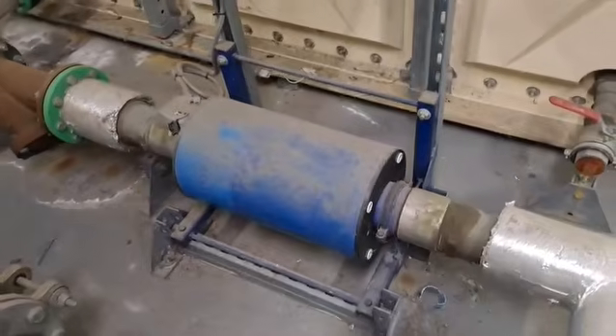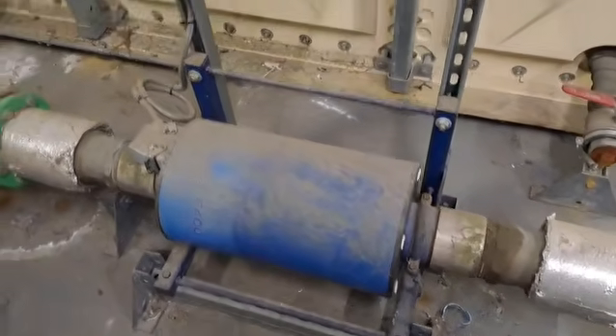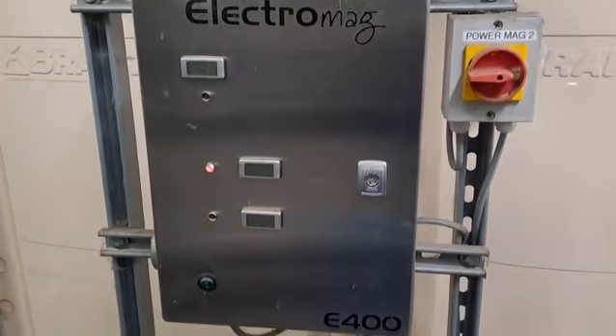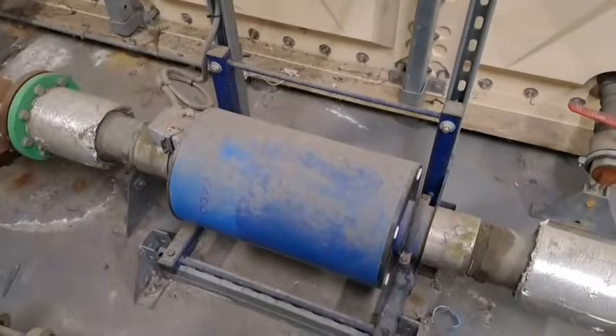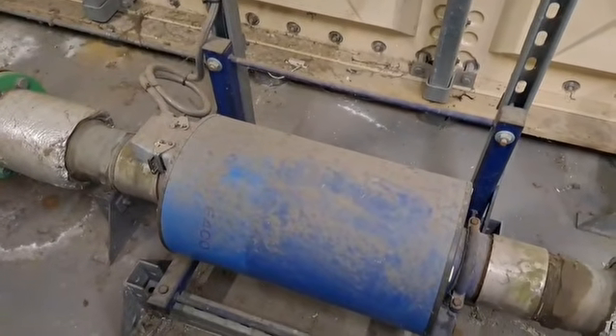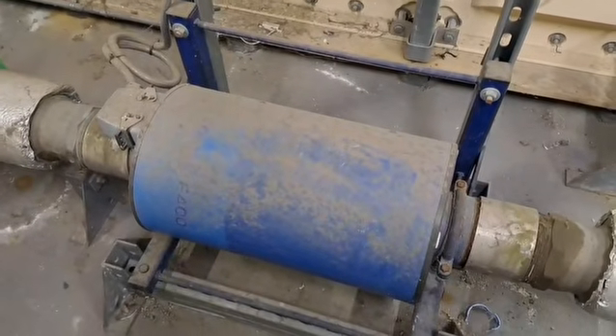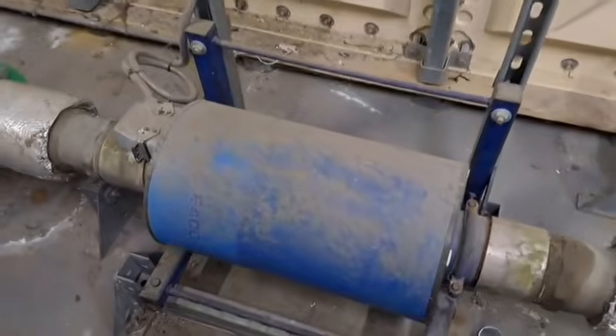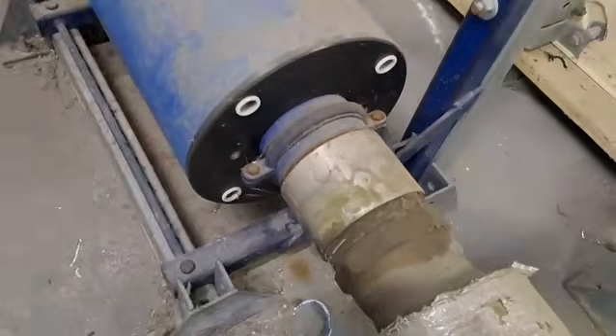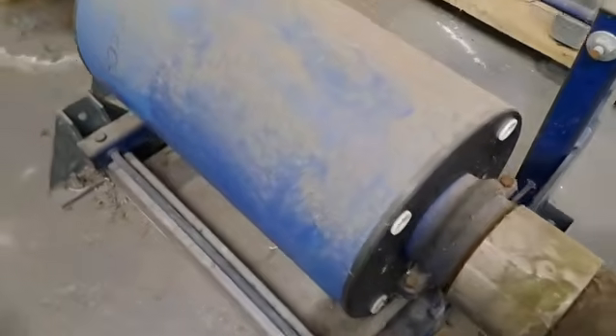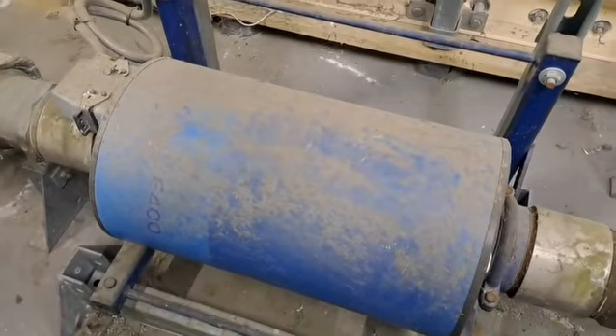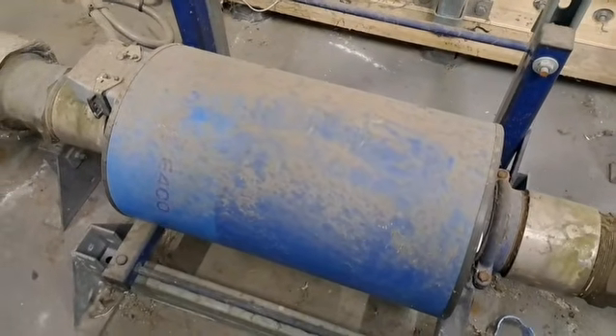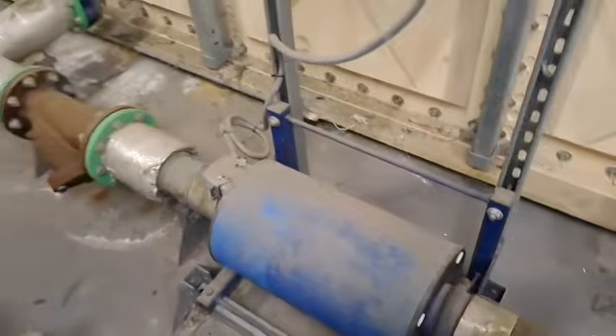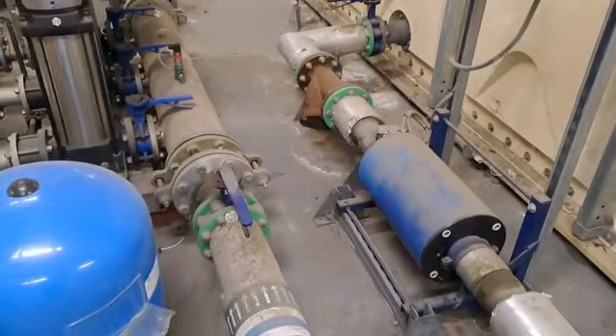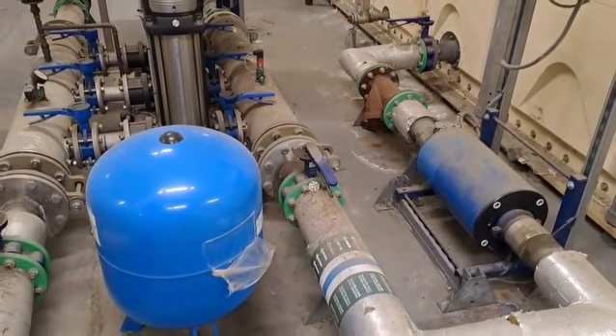and then as it comes along, you can see that we've got electromag E400s, and then down here you have the cylinder, the blue cylinder, which is the treatment coil, or you can call it a reactor. So this control panel here sends electromagnetic pulses to the pipe. Around the pipe you get the electromagnetic pulses from a coil. So it sort of alters the crystalline structures of the minerals, mainly calcium and magnesium, so it prevents limescale building up.